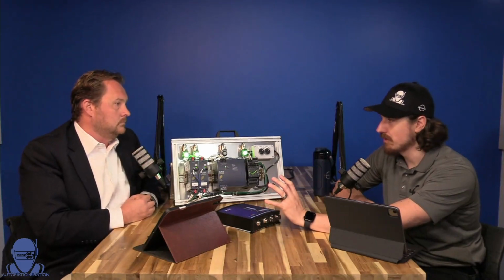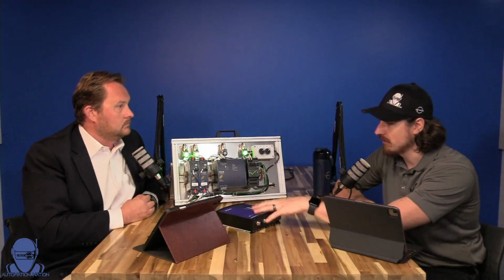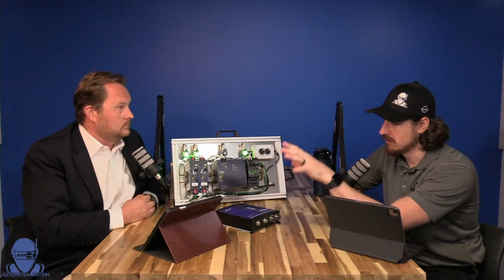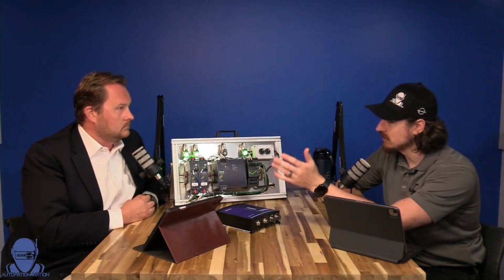This type of thing really allows a machine to be modular too. Let's say customers got modular conveyor systems. You can run your 3-phase out there that's powering your motor. Then it comes to this, all your sensors, your I/O, everything is on here. That whole piece is now completely separate and in its own closed loop from the rest of the control panel. So it's easy to build those in chunks or replace a whole one in chunks, instead of a whole new rewiring of the system or figuring out the new power system that has to come in for the whole machine in your giant 2-door cabinet.